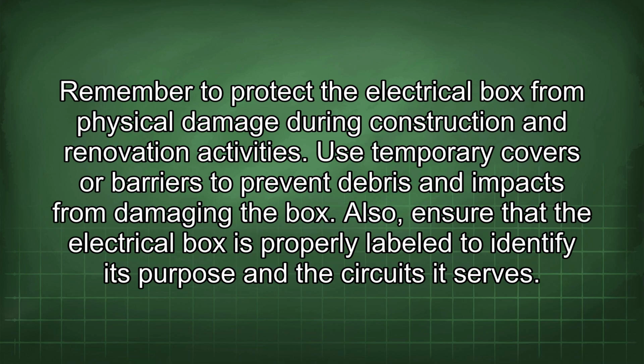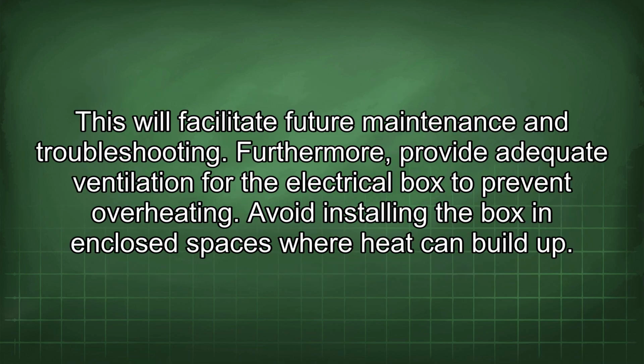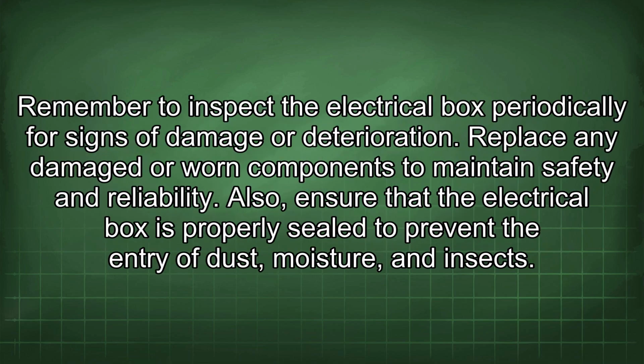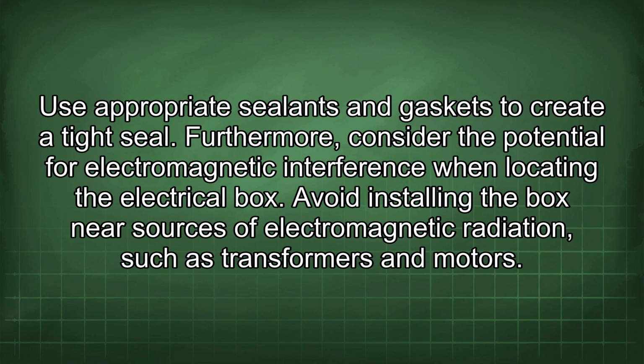Also, ensure that the electrical box is properly labeled to identify its purpose and the circuits it serves. This will facilitate future maintenance and troubleshooting. Furthermore, provide adequate ventilation for the electrical box to prevent overheating. Avoid installing the box in enclosed spaces where heat can build up. Remember to inspect the electrical box periodically for signs of damage or deterioration. Replace any damaged or worn components to maintain safety and reliability. Also, ensure that the electrical box is properly sealed to prevent the entry of dust, moisture, and insects. Use appropriate sealants and gaskets to create a tight seal.